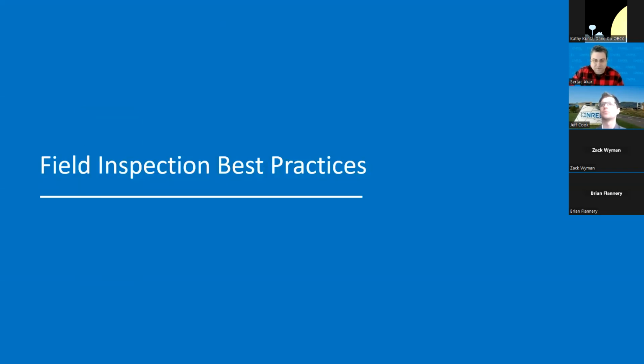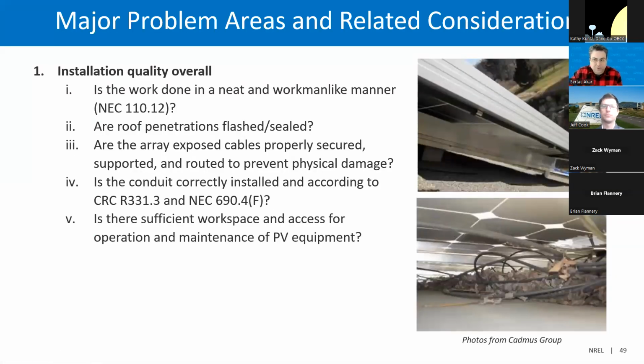All right, thanks, Jeff. So we will continue with some field inspection best practices. To start with, what are the major problem areas and related code considerations? One common area for code violation is the overall installation quality. The inspector should verify if the work is done in a neat and workmanlike manner. Roof penetrations must be flashed or sealed. The array exposed cables must be properly secured, supported, and routed to prevent physical damage. The conduits must be correctly installed, and there must be sufficient workspace and access for the operation and maintenance of the PV equipment.